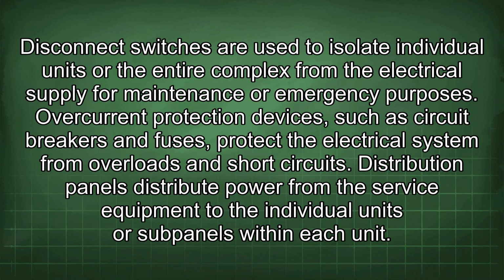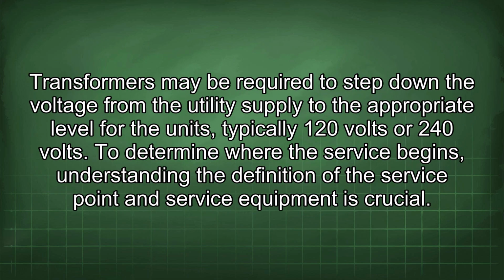Disconnect switches are used to isolate individual units or the entire complex from the electrical supply for maintenance or emergency purposes. Overcurrent protection devices, such as circuit breakers and fuses, protect the electrical system from overloads and short circuits. Distribution panels distribute power from the service equipment to the individual units or subpanels within each unit. Transformers may be required to step down the voltage from the utility supply to the appropriate level for the units, typically 120 volts or 240 volts.